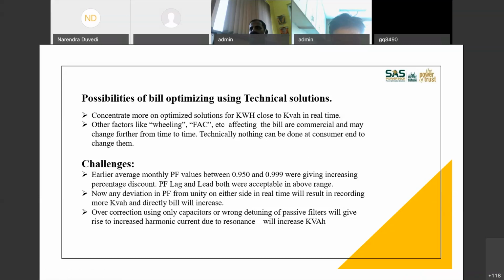So your real-time power factor is becoming more and more important rather than the average power factor over a month. Earlier, some adjustments were possible. During the MSEDCL audit, we saw a few people who used to keep a leading power factor throughout the day and disconnect all the capacitors during the night and run without capacitors, because their machinery was getting affected by harmonics. Still their average power factor was unity and they were getting full discounts. Now such a thing cannot be done with kVAh billing. Correcting using only capacitors, or wrong detuning of passive filters, will give rise to increased harmonic current due to resonance, which will increase kVAh. So again, this is also a challenge.